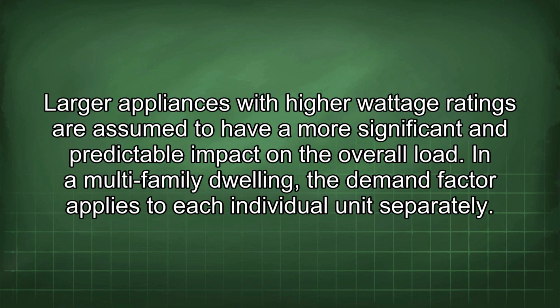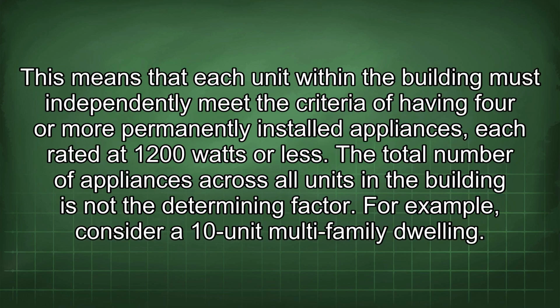In a multi-family dwelling, the demand factor applies to each individual unit separately. This means that each unit within the building must independently meet the criteria of having 4 or more permanently installed appliances, each rated at 1200 watts or less. The total number of appliances across all units in a building is not the determining factor.